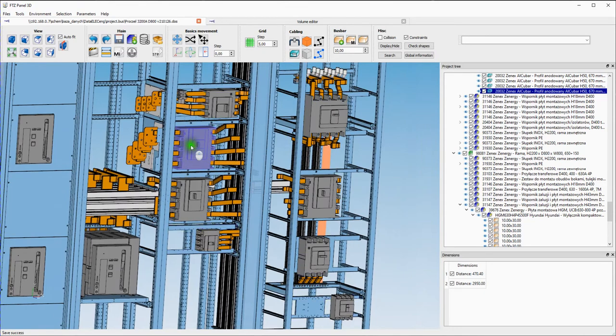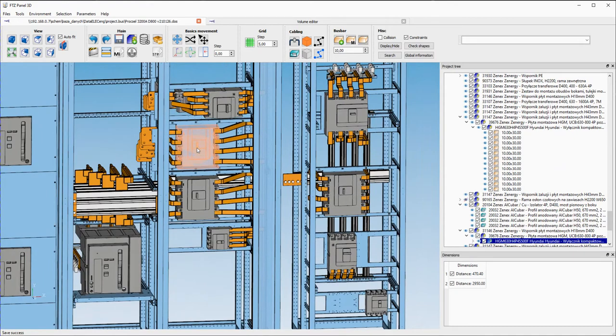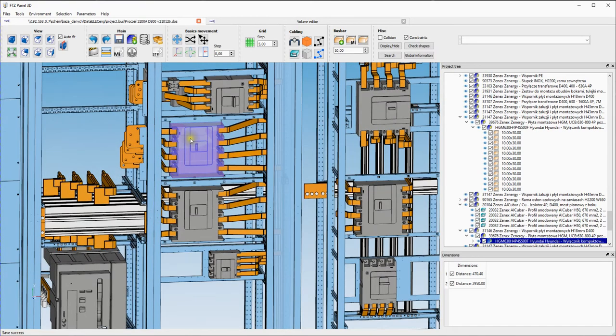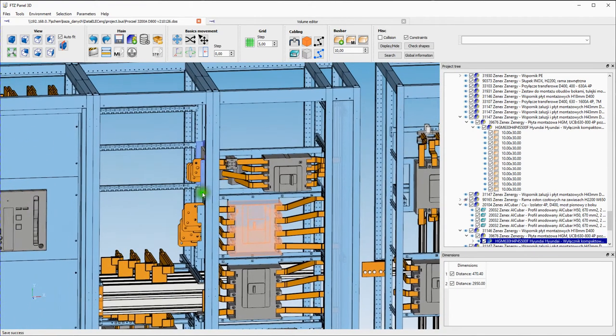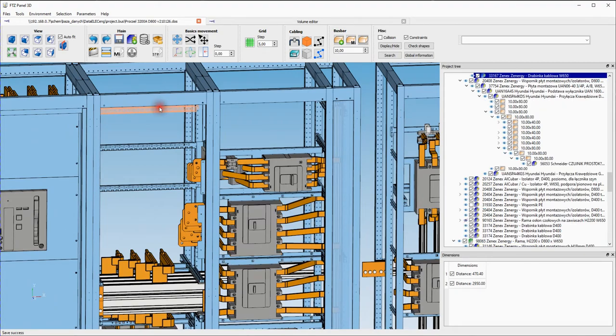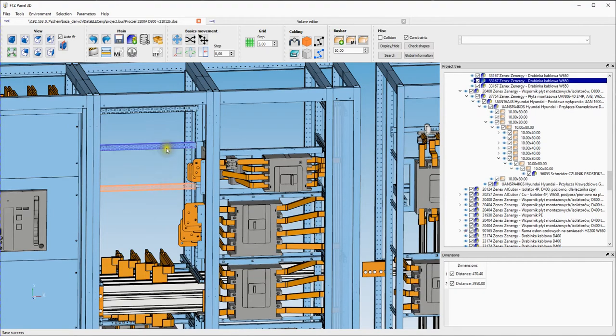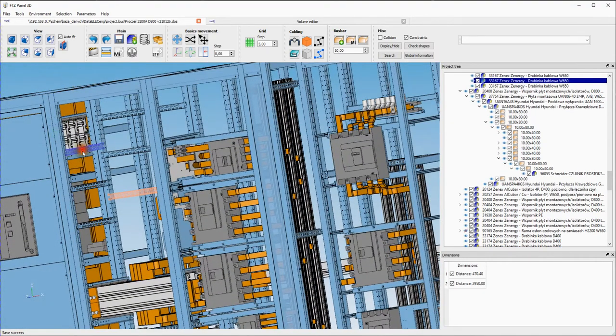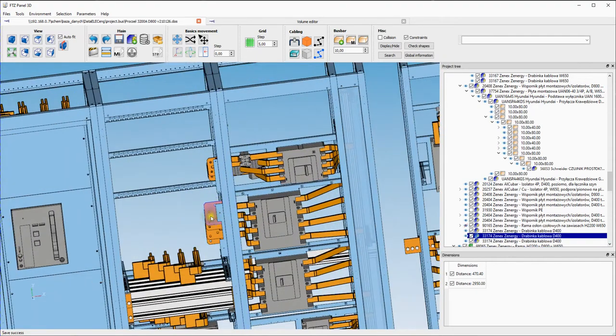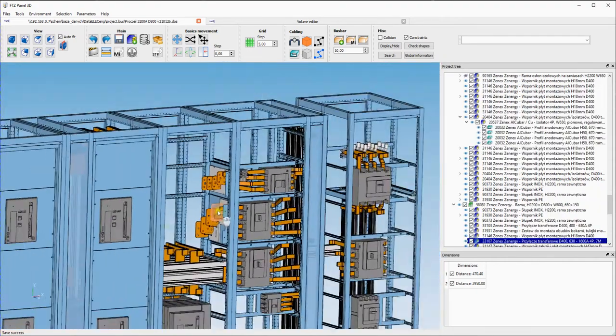So the 500 ampere incoming from the generator or co-generator, the cable can go here from the top. You can tie it to the cable ladders. It can go on the right side, tie it to the cable ladders, and then go to the big terminals. Everything is nice here with the cables.